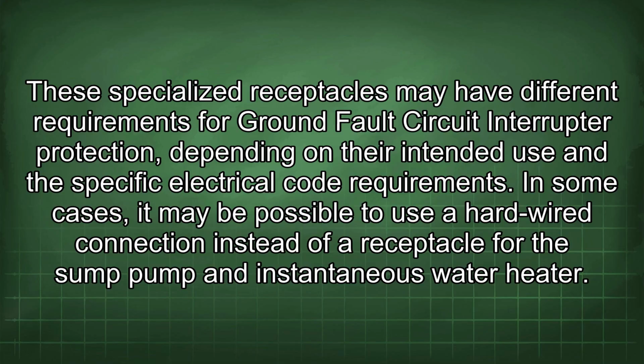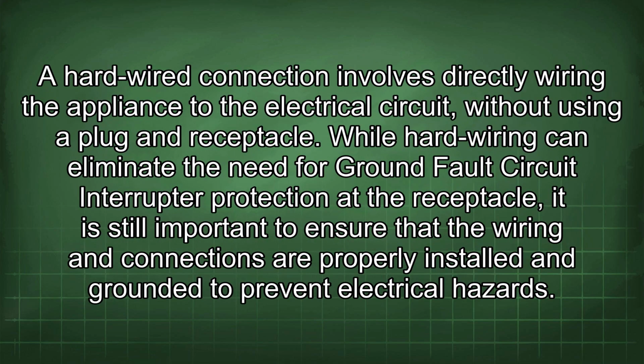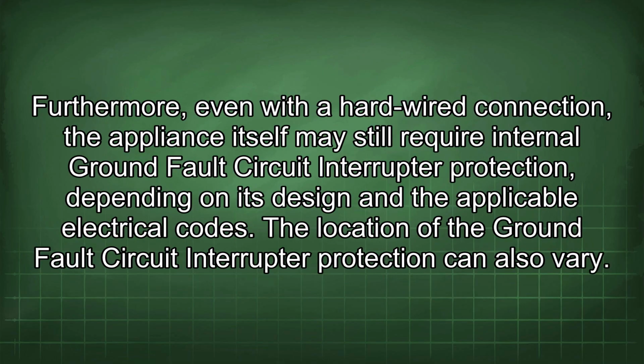These specialized receptacles may have different requirements for ground fault circuit interrupter protection, depending on their intended use and the specific electrical code requirements. In some cases, it may be possible to use a hard-wired connection instead of a receptacle for the sump pump and instantaneous water heater. A hard-wired connection involves directly wiring the appliance to the electrical circuit without using a plug and receptacle. While hard wiring can eliminate the need for ground fault circuit interrupter protection at the receptacle, it is still important to ensure that the wiring and connections are properly installed and grounded to prevent electrical hazards. Furthermore, even with a hard-wired connection, the appliance itself may still require internal ground fault circuit interrupter protection, depending on its design and the applicable electrical codes.